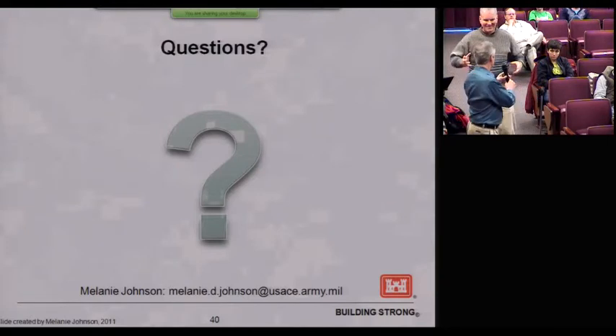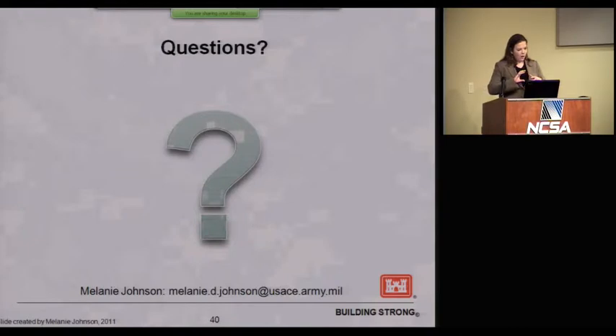Absolutely. One thing being looked at a lot with SPIDERS is how we characterize that communication so we can restrict it to basically what they need to know and what we need to know, so we can do good monitoring to determine if something outside those parameters has been generated by a third party attack or something along those lines. So what we envision as communication is perhaps pricing data coming from the utility, and if we need to disconnect or reconnect, communicating that to the utility for their preparation. There's also interest in the microgrid doing its own sensing to determine if something is going wrong with the grid so it could island preemptively. Those are probably the major kinds of communication.